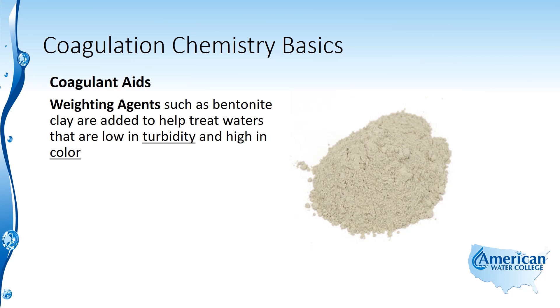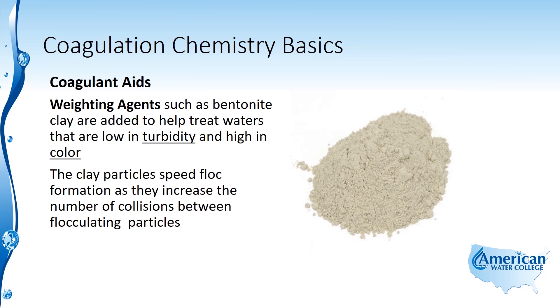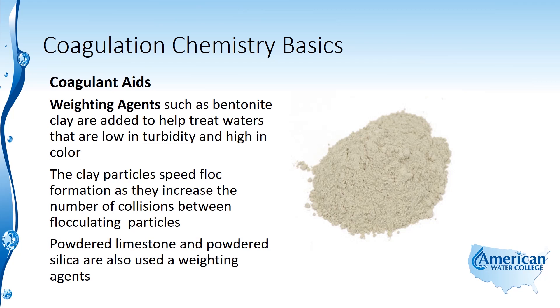Weighting agents such as bentonite clay are added to help treat waters that are low in turbidity and high in color. The coagulation and flocculation process actually works better on waters that are high in turbidity, so if turbidity is low you can add artificial turbidity in the form of bentonite clay or other weighting agents to also help remove color. The clay particles speed floc formation by increasing the number of collisions between flocculating particles — particle collision is key, which is why we need appropriate mixing energy in the flocculation process. Powdered limestone and powdered silica are also used as weighting agents.